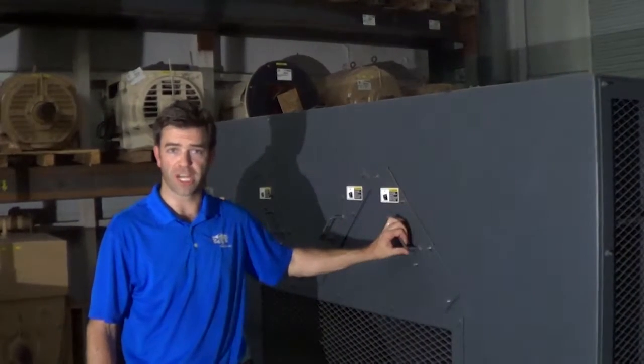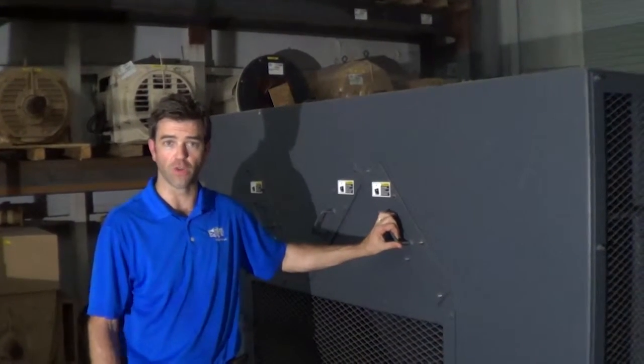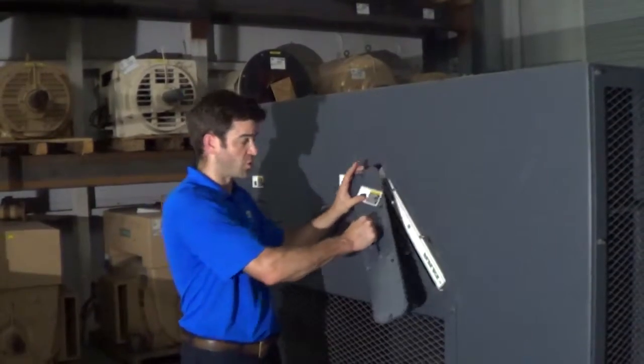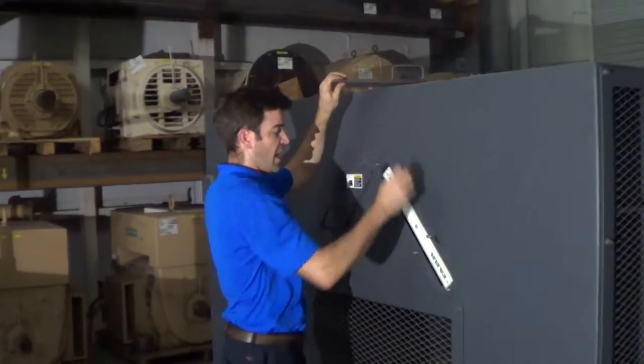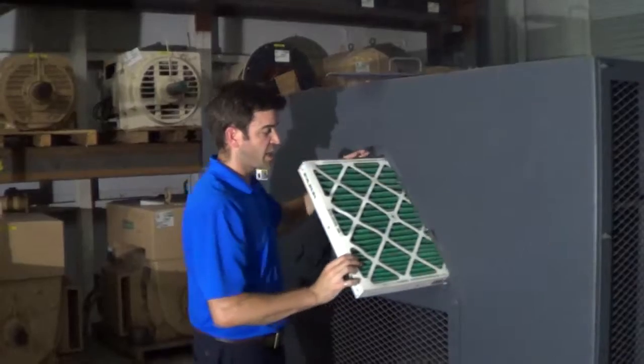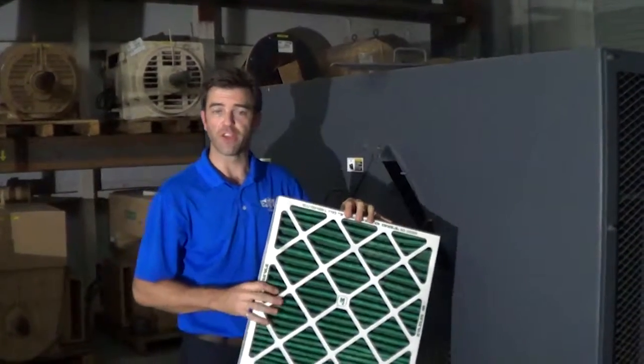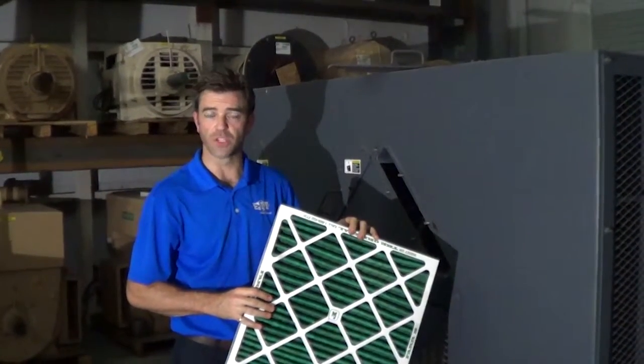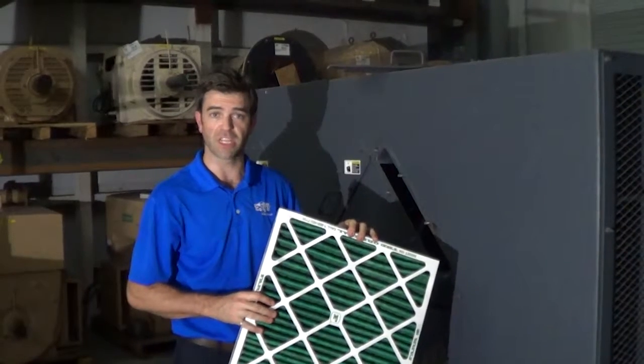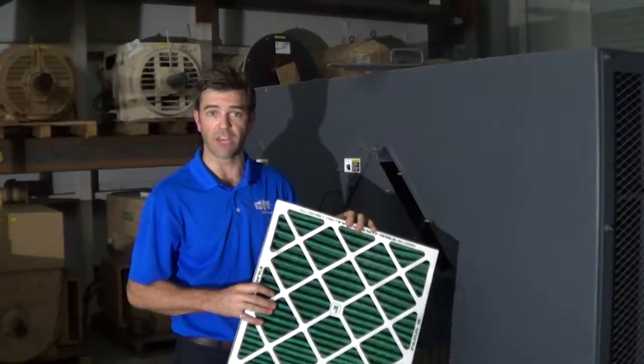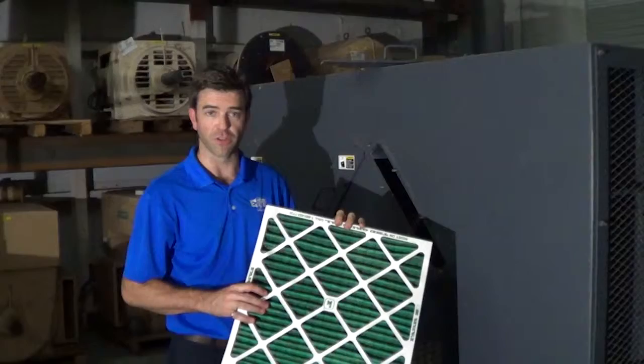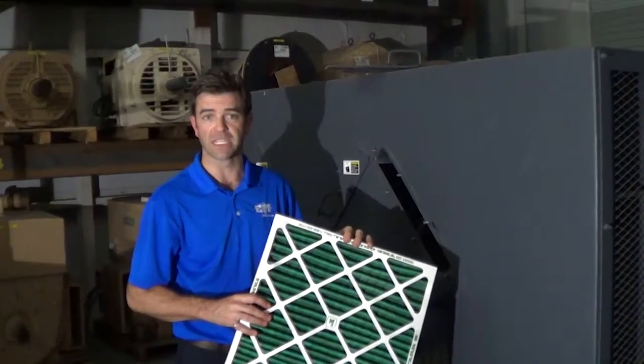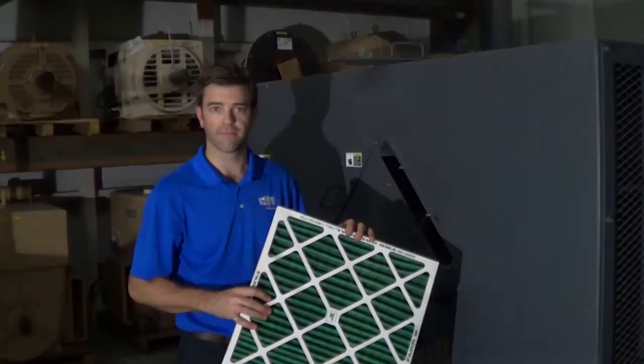This is a weather-protected 2 or WP2 enclosure, and so it has an array of filters. We remove the cover and inspect the filters. In this case, we're using paper filters. If the equipment is installed with stainless steel filters, they can be cleaned with compressed air or steam as necessary and reinstalled. These paper filters should be discarded and replaced at any outage.